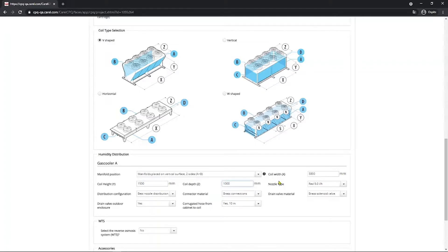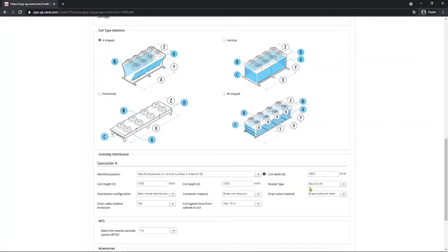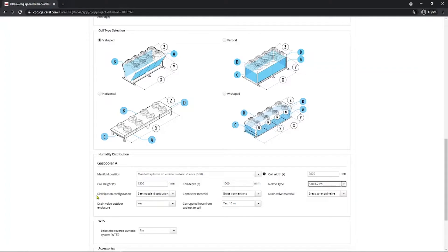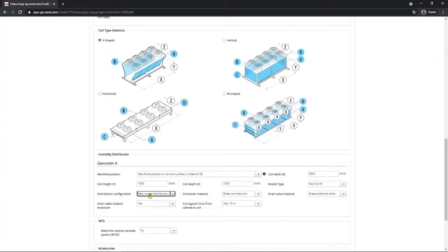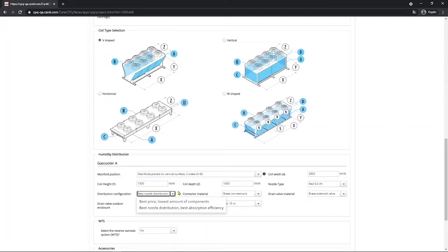Nozzle type. Then you select the size of a nozzle based on the load. So we have the 5 liters per hour, 7.5 liters per hour and 15 liters per hour. The default is red and that's the value you should start with. Distribution configuration depends on the project. The desired solution could be the one that offers the best filling of the coil and therefore the highest cooling performance, or the simplest system and therefore the one with the fewest components. So the selection will be different if you select one or the other. The default value is best nozzle distribution, best absorption efficiency.